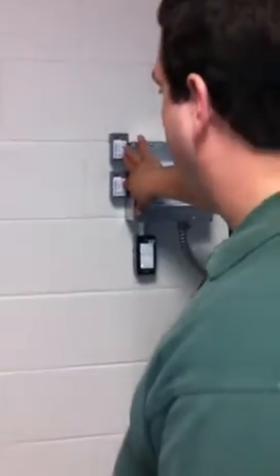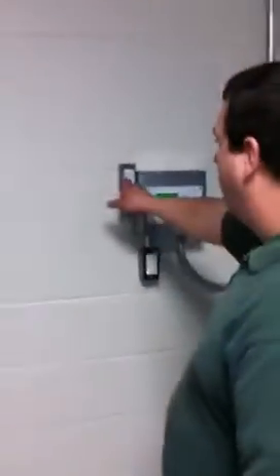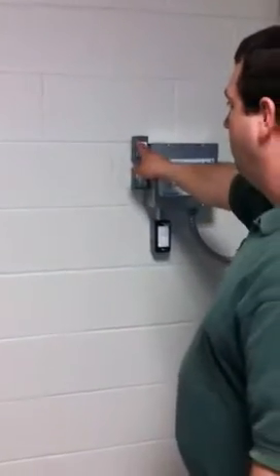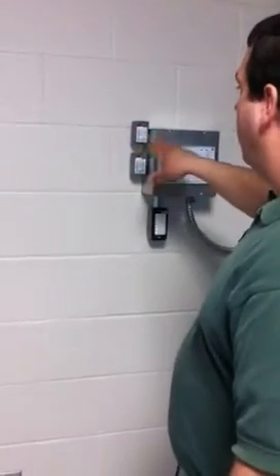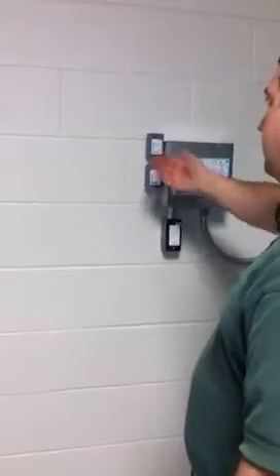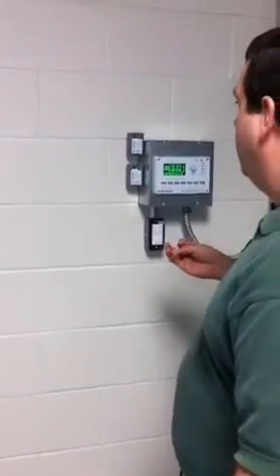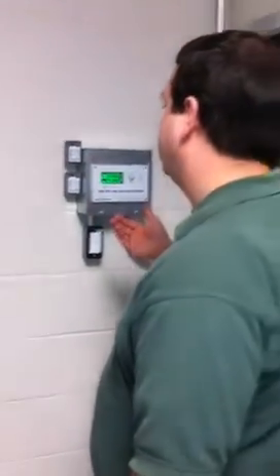These two relays on the side, like I said in the other video, are the contacts from the BMS system. The BMS guy has labeled them. This is your exterior lights, these are your interior lights. When the pilot light is on, that means the relay is engaged or it's getting a signal from the BMS system, which has an override of the time clock schedule.